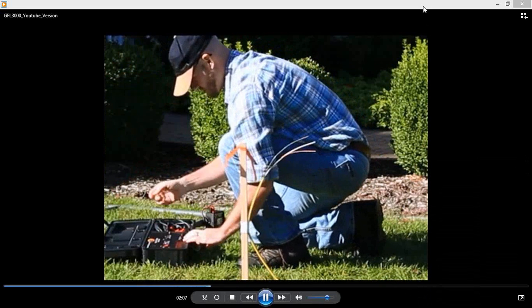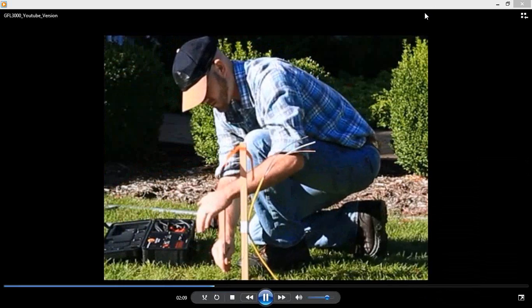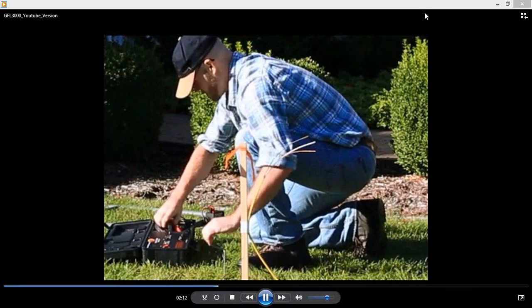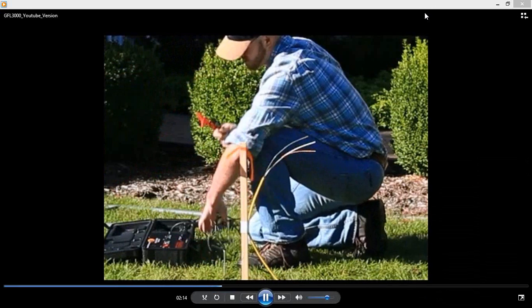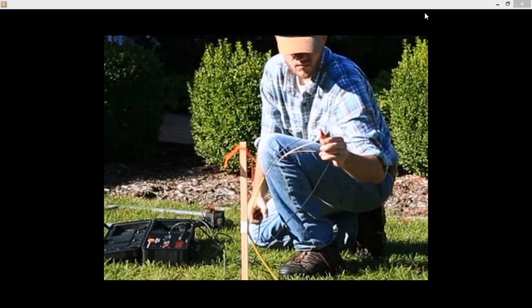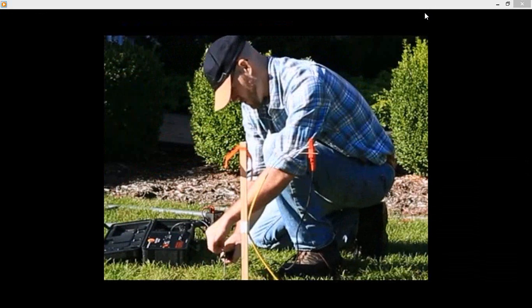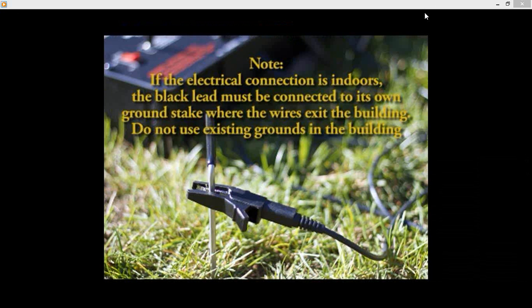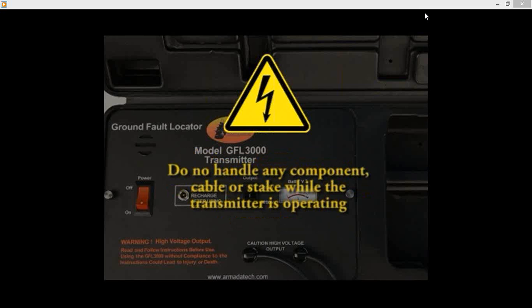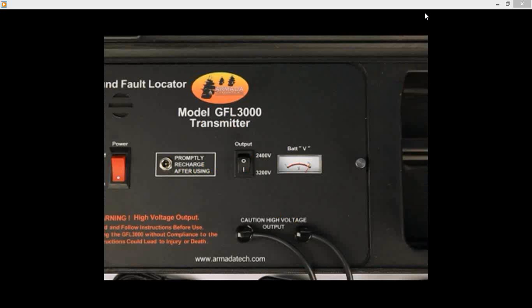At either end of the cable, and with the transmitter off, connect the black lead to the ground stake and push the stake into the ground as deeply as possible. Connect the red lead to the cable that is being tested. Note that if the cable is indoors, the black lead must be connected to its own ground stake where the wires exit the building. Do not use existing grounds in the building. Before turning on the transmitter, be sure no one is touching the stake, cable, or leads. When turned on, the transmitter will produce a beeping sound indicating current is being transmitted.